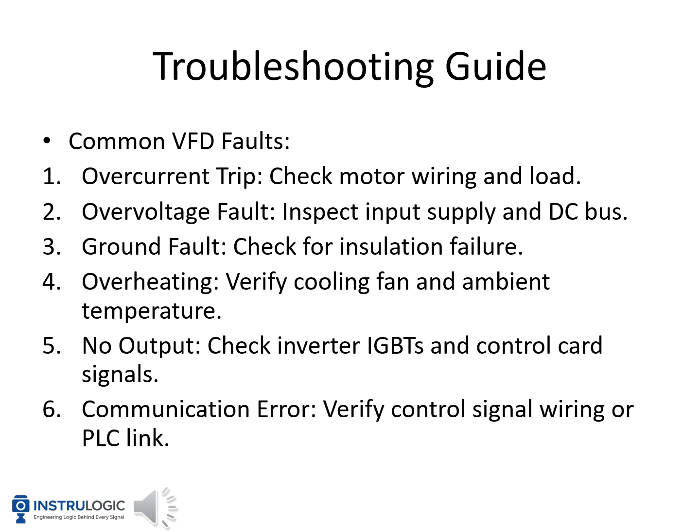Let's look at some common VFD faults and how to troubleshoot them. Overcurrent trip — this usually happens when the motor draws too much current; check motor wiring and make sure the load is not jammed or too heavy. Overvoltage fault — inspect the input supply and the DC bus, as high voltage spikes can cause this. Ground fault — this indicates insulation failure; check motor cables and insulation resistance. Overheating — verify that the cooling fan is working and ambient temperature is within limits. No output — check the inverter section, especially the IGBTs, and confirm control signals from the logic board. Communication error — verify wiring and communication settings. Regular checks and preventive maintenance can reduce these faults.